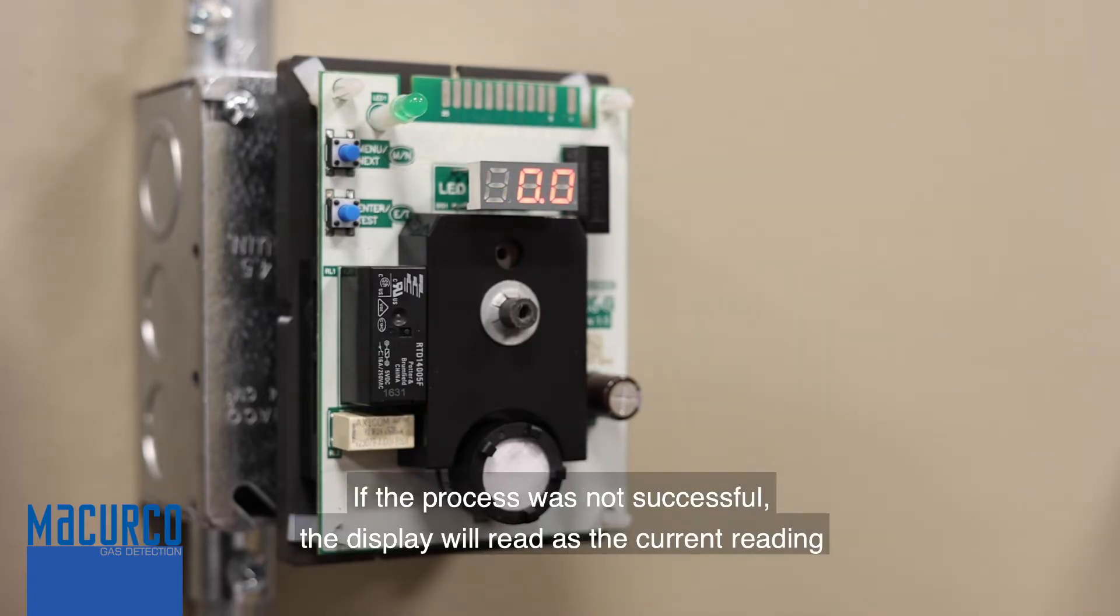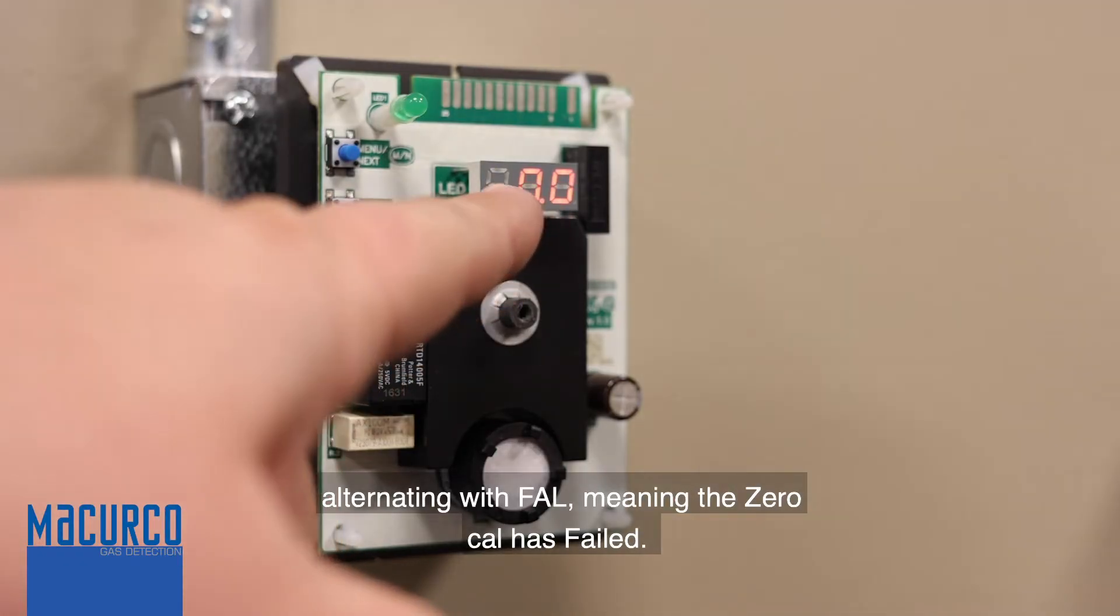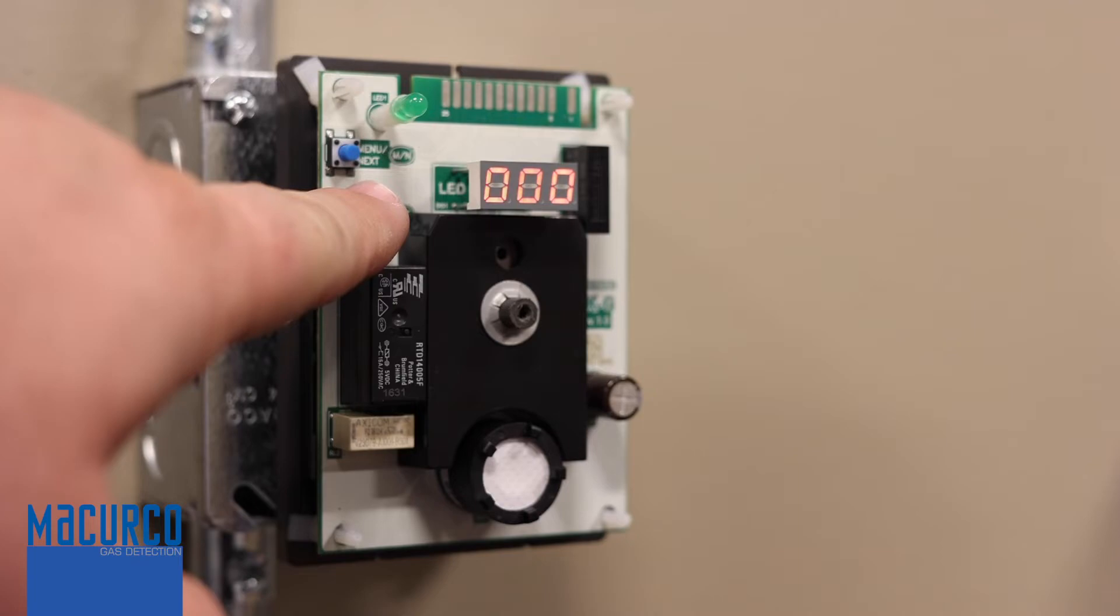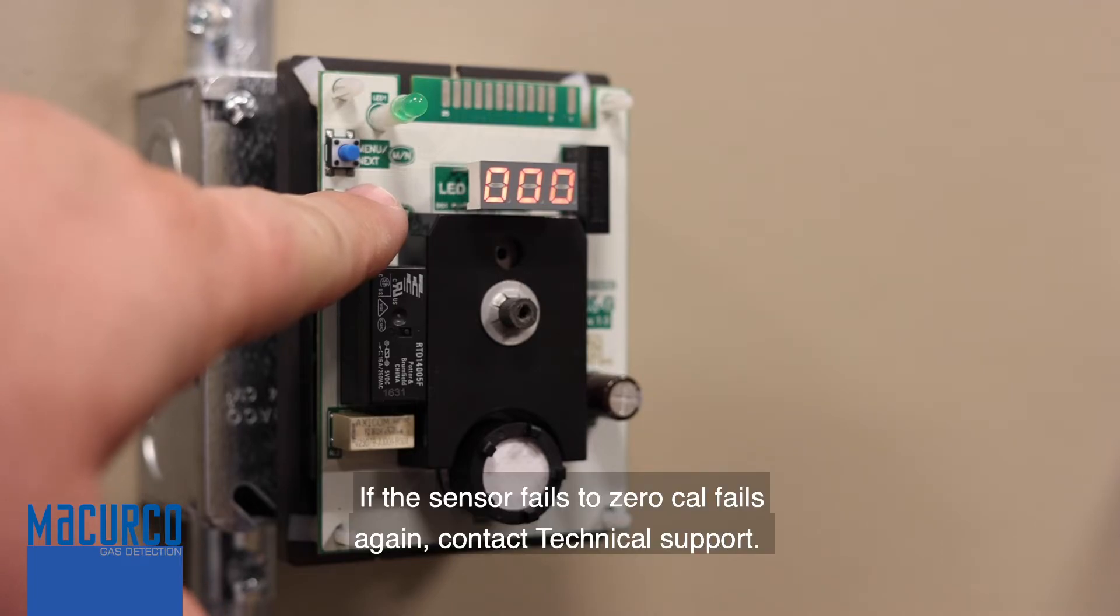If the process was not successful, the display will read as the current reading alternating with FAL, meaning the zero cal has failed. If this occurs, repeat the steps. If the sensor fails to zero cal again, contact technical support.